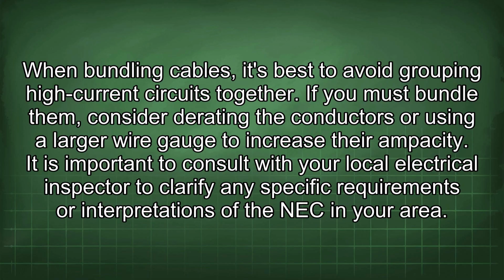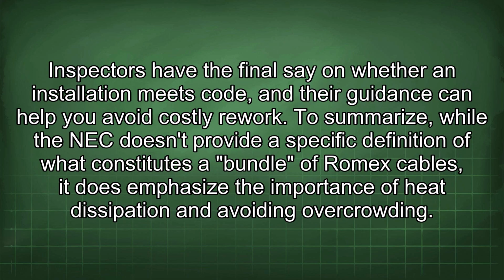If you must bundle them, consider derating the conductors or using a larger wire gauge to increase their ampacity. It is important to consult with your local electrical inspector to clarify any specific requirements or interpretations of the NEC in your area. Inspectors have the final say on whether an installation meets code, and their guidance can help you avoid costly rework.